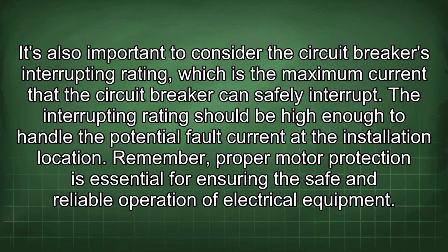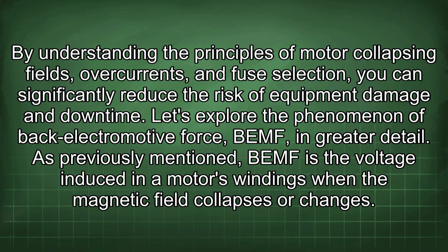It's also important to consider the circuit breaker's interrupting rating, which is the maximum current that the circuit breaker can safely interrupt. The interrupting rating should be high enough to handle the potential fault current at the installation location. Remember, proper motor protection is essential for ensuring the safe and reliable operation of electrical equipment. By understanding the principles of motor collapsing fields, overcurrents, and fuse selection, you can significantly reduce the risk of equipment damage and downtime.